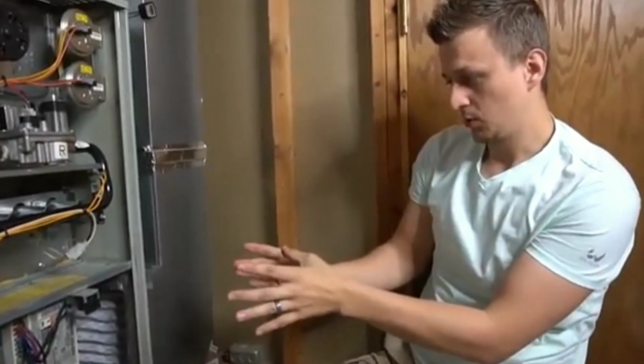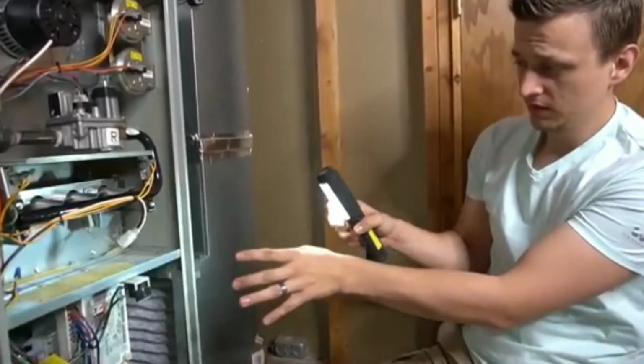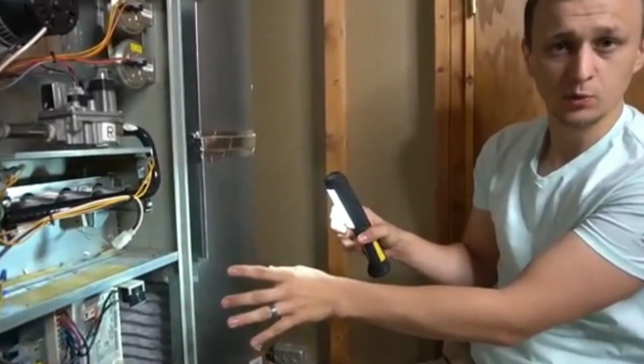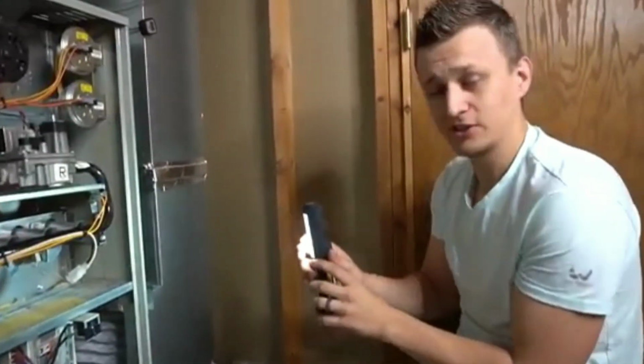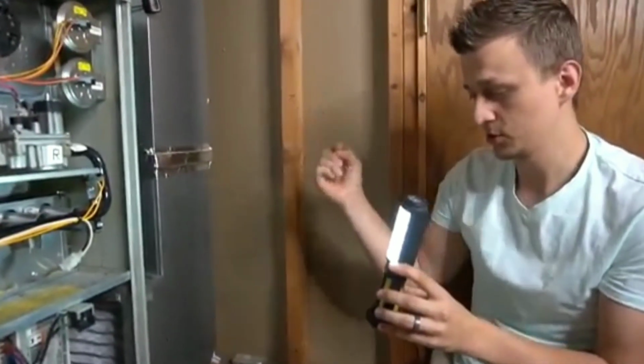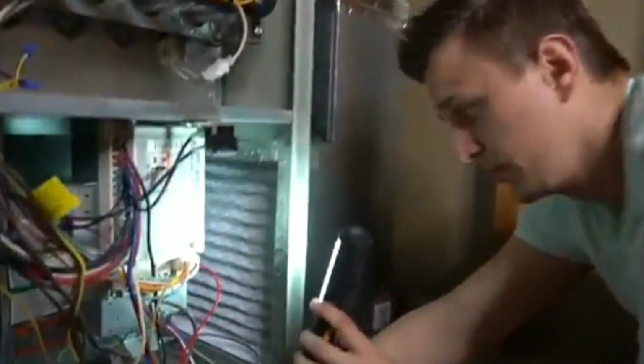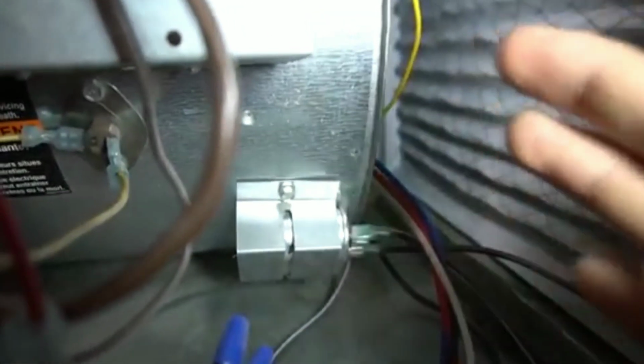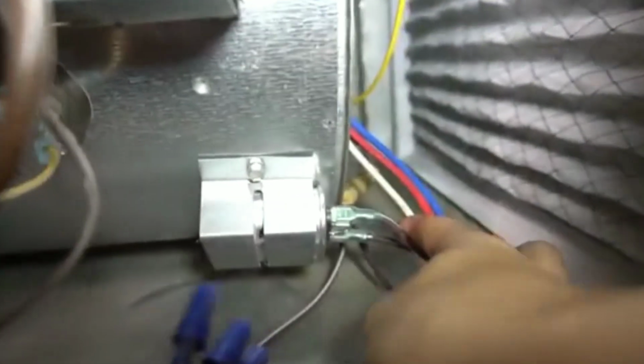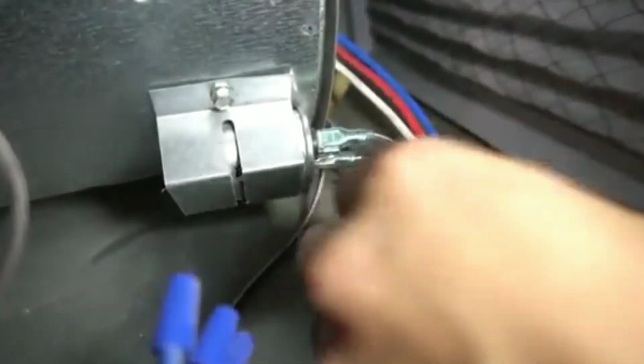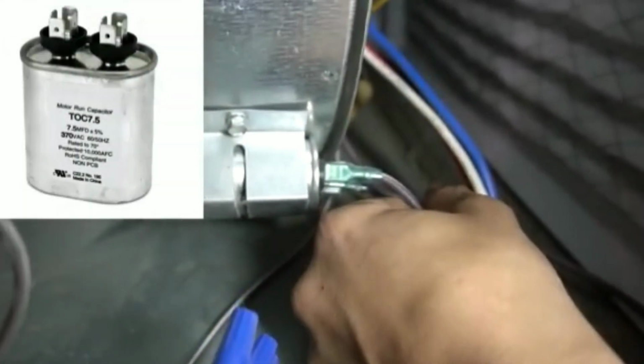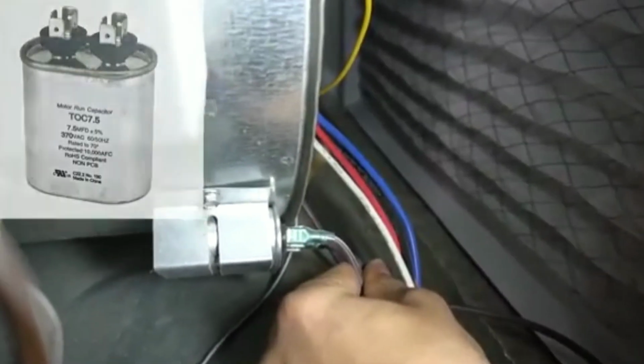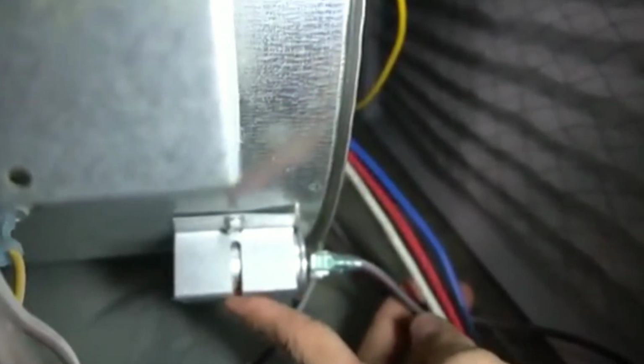And while we're on the topic of the blower wheel, most of them, unless you have a variable speed one, will have a capacitor, just like the capacitor that you saw in the air conditioner outside. It can be in different locations. Usually it'll be mounted towards the front, either on the bottom right here or on the side. Sometimes, if you're not lucky, it'll be way in the back there. But it has two brown wires going to it. This is just a single capacitor, meaning it's just for the fan, whereas the one outside is for the fan and the compressor. That's why it's called a dual capacitor. But this capacitor is the same as outside.